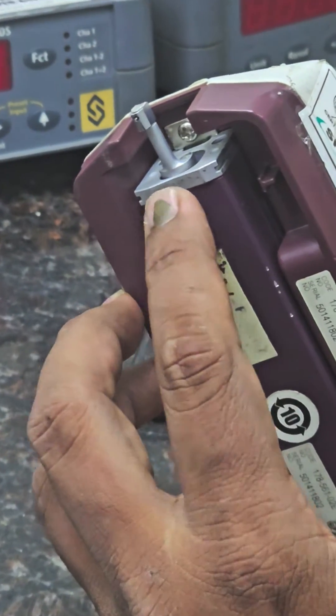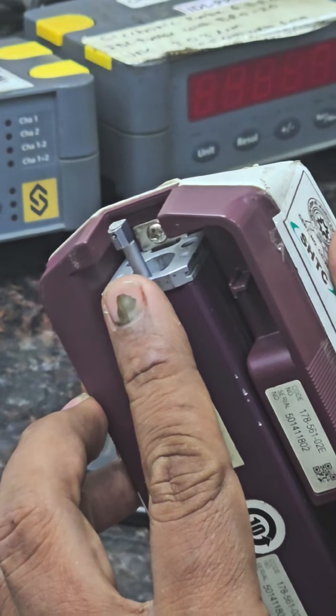In that way the probe will be saved, and the life of the probe will be improved. See, the probe is going to its home position. The machine is off — it will only work after removing the charger cable. Otherwise it cannot work.